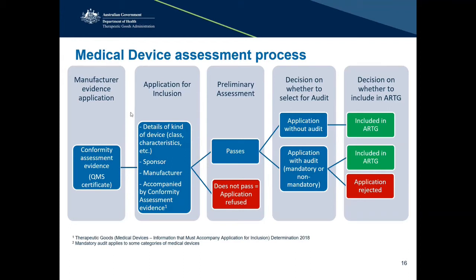So in terms of the medical device inclusion process, a sponsor will first submit evidence of conformity assessment, and this is usually a certification from a competent authority or body who has inspected and certified that the manufacturer's QMS meets all legislative requirements. The sponsor then submits an application for the inclusion and provides further details such as manufacturer details, GMDN code, the classification, and any other relevant documentation. And a preliminary assessment is then made on the application, and the delegate will have 20 business days to select an application for audit if there are concerns. However, do note that there are mandatory audits that apply to certain categories of medical devices. And so if the application meets all legislative requirements, the application is then included in the ARTG.